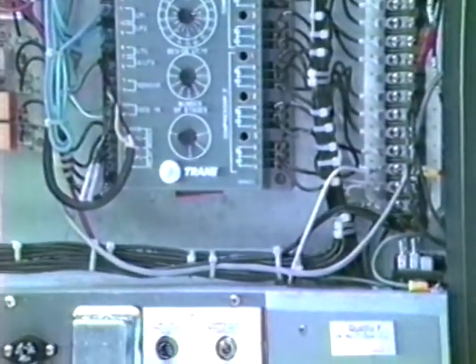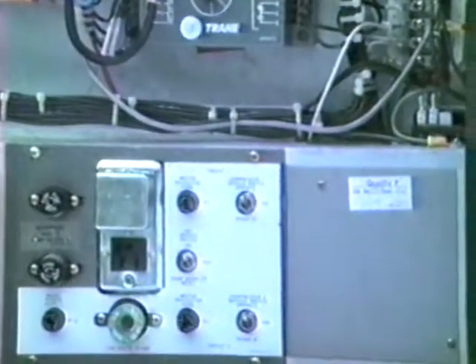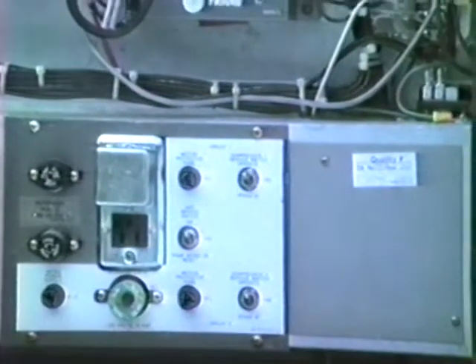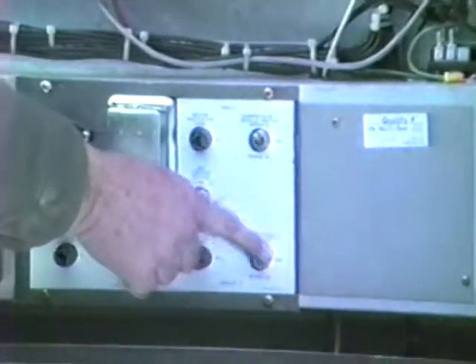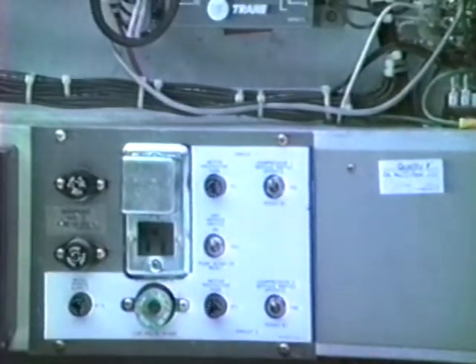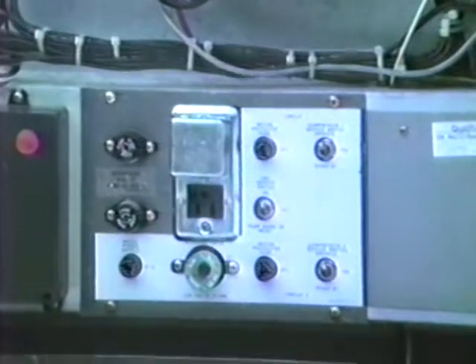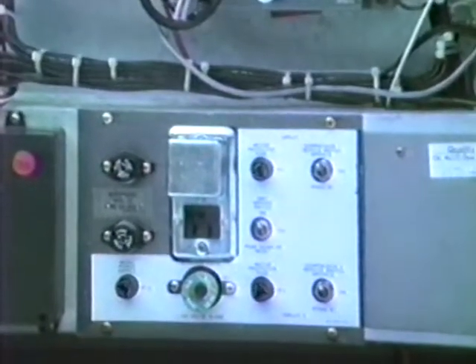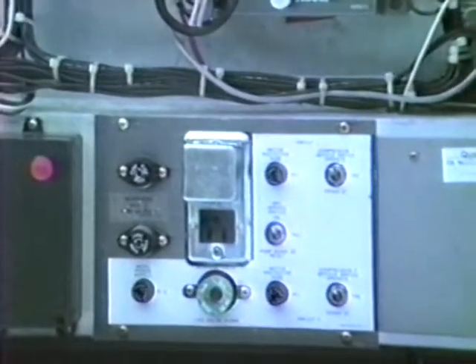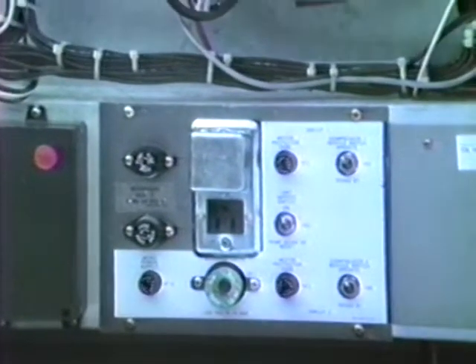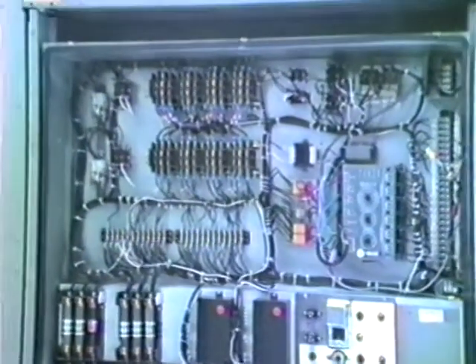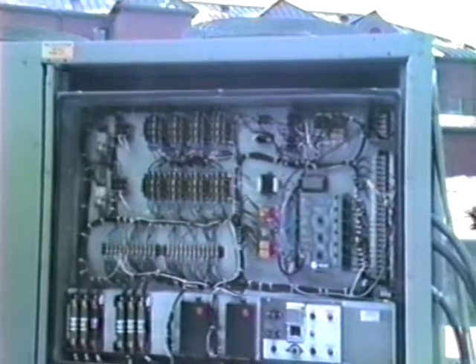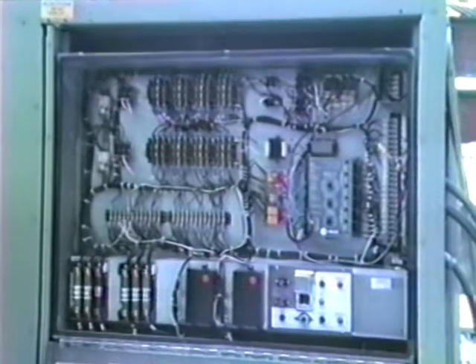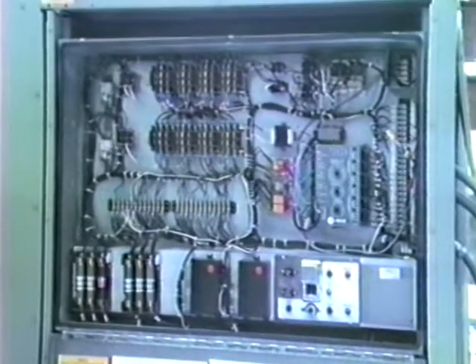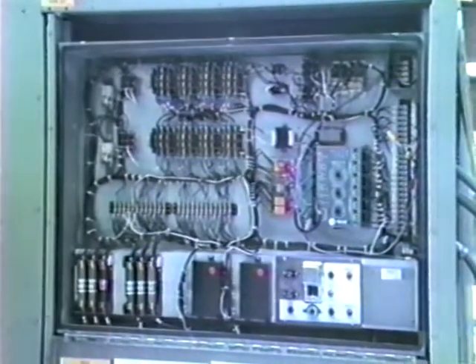Wonderful, Mark. Roy, if you would point out the compressor service switches. Compressor 1 service switch, compressor 2 service switch. Wonderful, Mark. We can see right in the center there is a 120 volt convenience plug for lights, tools, and whatever. Inside this control panel are the condenser fan contactors, circuit fuses, all the basic electrical components for operating this chiller.